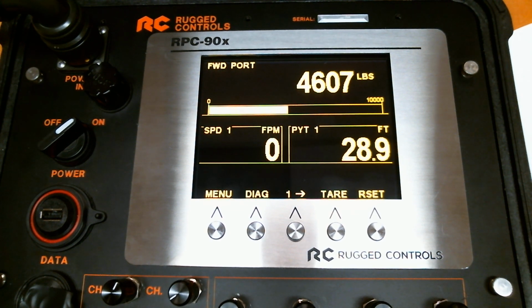I'm with Rugged Controls. Today we'd like to talk about how to calibrate an RPC-90x for payout and speed measurements on single winch applications. We recommend two methods. One method is mathematical, the other method, like the tension calibration, is a live calibration.